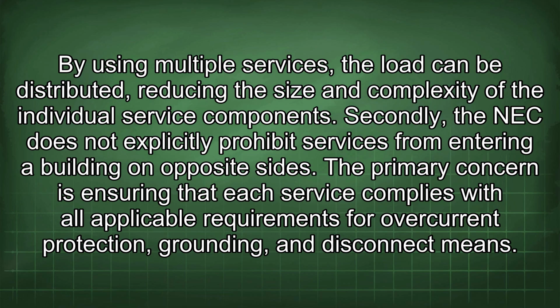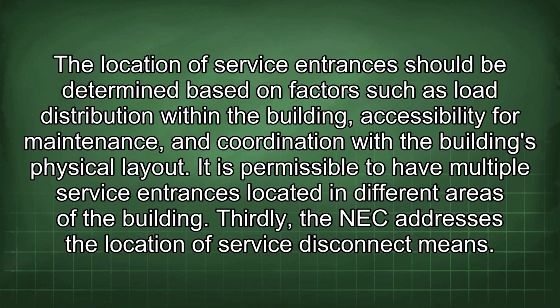Secondly, the NEC does not explicitly prohibit services from entering a building on opposite sides. The primary concern is ensuring that each service complies with all applicable requirements for overcurrent protection, grounding, and disconnect means. The location of service entrances should be determined based on factors such as load distribution within the building, accessibility for maintenance, and coordination with the building's physical layout. It is permissible to have multiple service entrances located in different areas of the building.